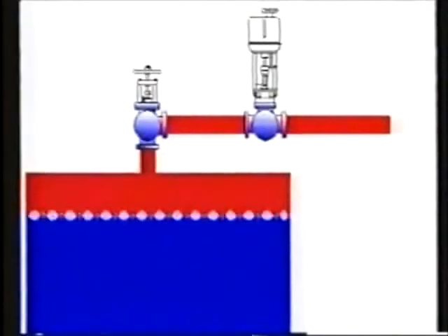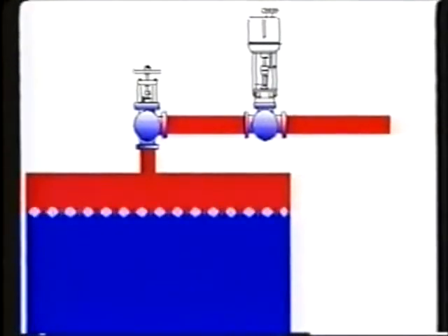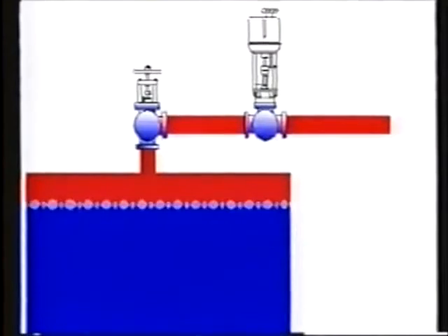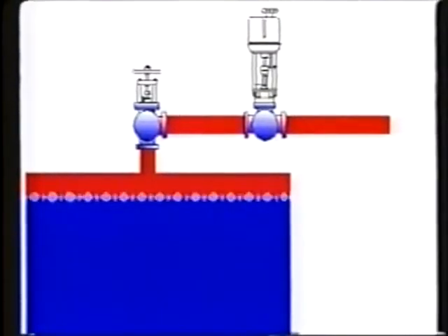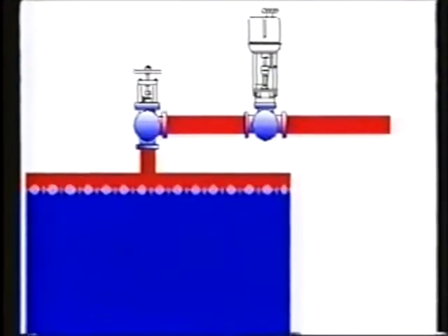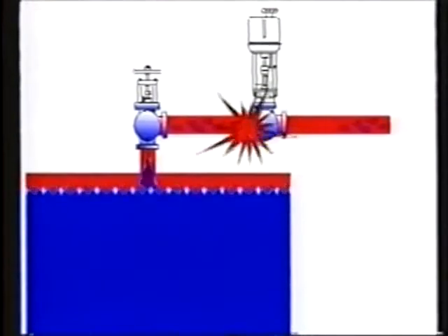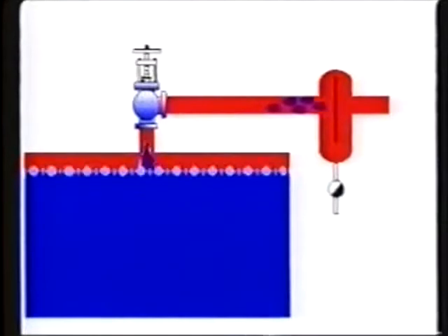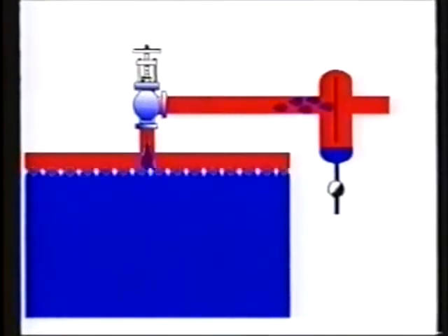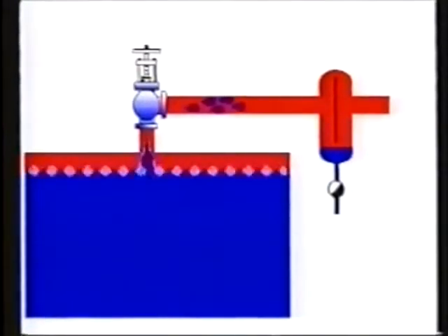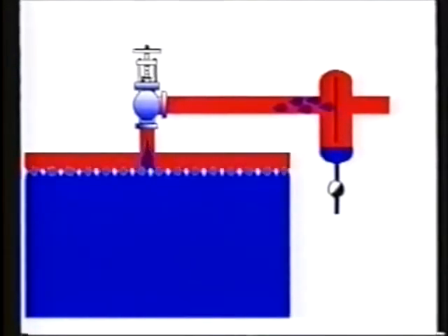If the steam demand is increased beyond the limit of the boiler's maximum steam generation rate, the effect can be spectacular as well as potentially dangerous. If water is allowed to carry over with steam and accumulate in the steam main, it can cause severe damage to valves and fittings through water hammer and could even cause injury to personnel. Impurities in the water can also cause contamination of the steam main, control valves, heat exchangers, and steam traps.